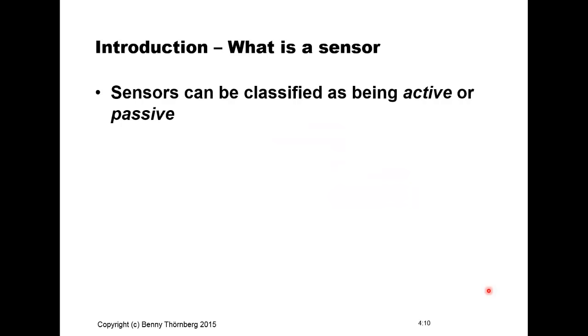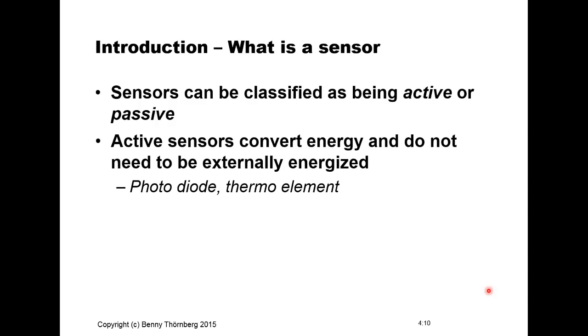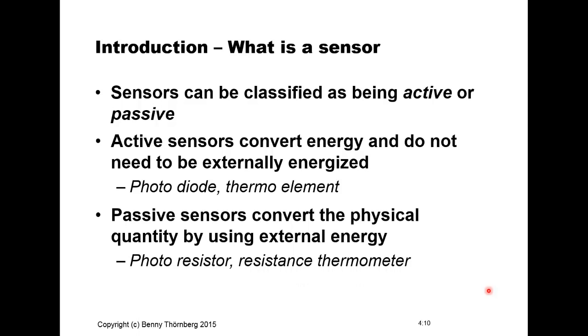We can further classify sensors into being either active or passive. An active sensor can convert the energy of the input and does not need any external energy to work. Examples of such are photodiodes for measuring light intensity or a thermal element for measuring temperature difference. A passive sensor, on the other hand, converts a physical quantity by using external energy, so we need an external power supply to make it work. Examples of such are photoresistors or different kinds of resistance thermometers.